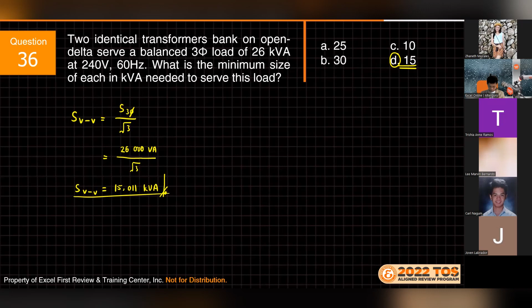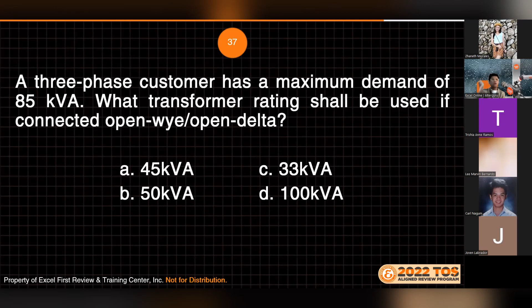Next to it is number 37. A three-phase customer has a maximum demand of 85 kVA. What transformer rating shall be used if connected open Y, open delta? Check niyo lang dito yung pinakadulo. Kung open Y kasi siya, natanggal yung isa kasi Y-connected siya doon. Importante yung sa load side, so ganun din yung gagawin natin for that one.